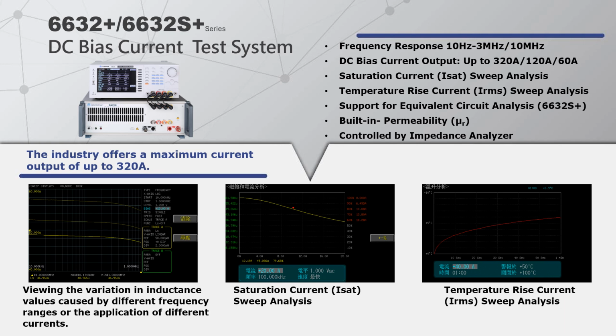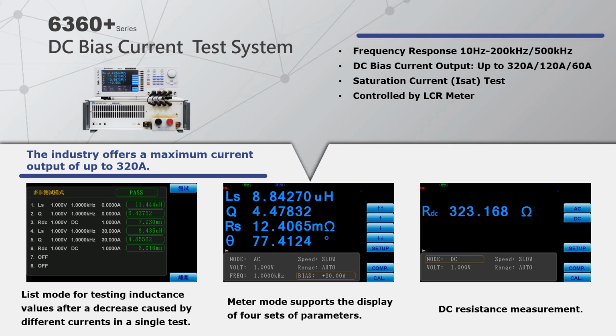The images below provide an introduction to some scan analysis functions, where different currents are applied to observe the resulting changes in inductance values. This includes the analysis of the saturation level of the current and the scanning analysis of temperature rise current. The 6360 Plus series DC bias current source test system is primarily composed of an LCR meter with a built-in DC bias current source. The frequency response can reach up to 500,000 Hz, and the DC bias current source output reaches a maximum of 320 amps.